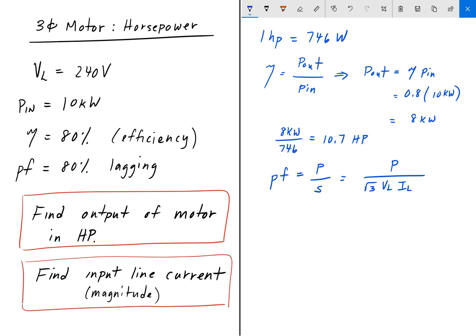And so we can rearrange this formula here to solve for the line current, I L. And that comes out to P over the square root of 3, V L, times the power factor.